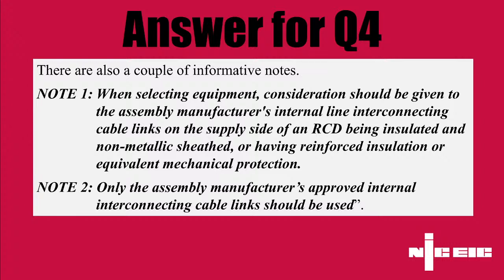following your manufacturer's instructions. To my mind, no manufacturer has ever stated that their board, their consumer unit, can't be used on a TT system because of the internal wiring, but according to those notes, we should get confirmation. What I would add to that is, not only when referring to manufacturer instructions, you're also determining that the connections are torqued up to the right settings as well.